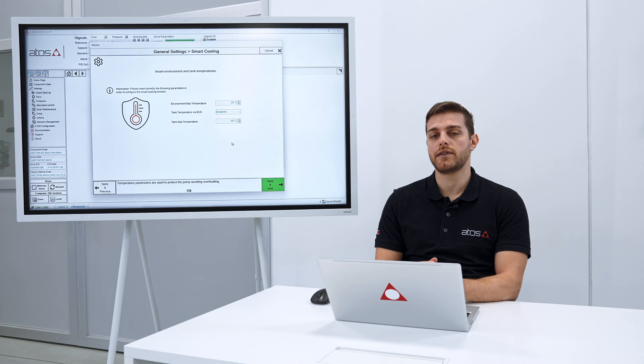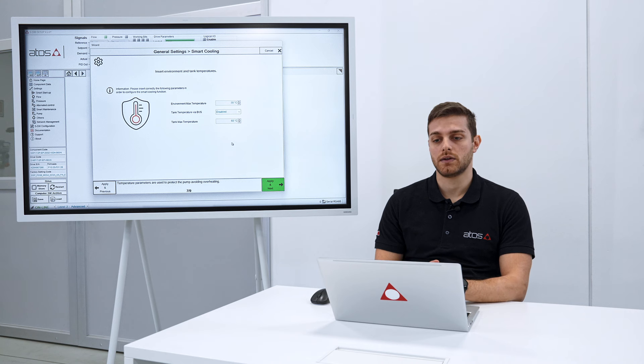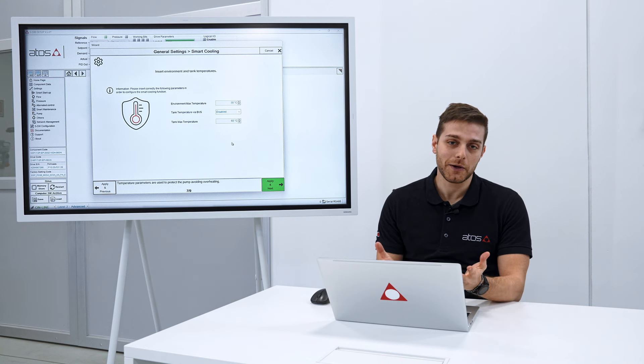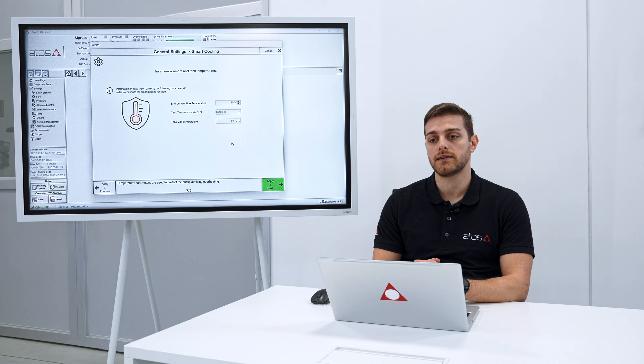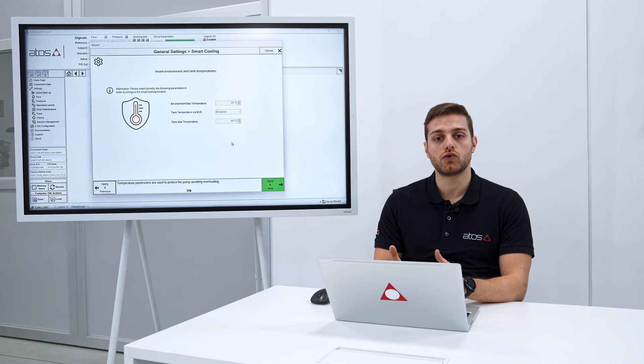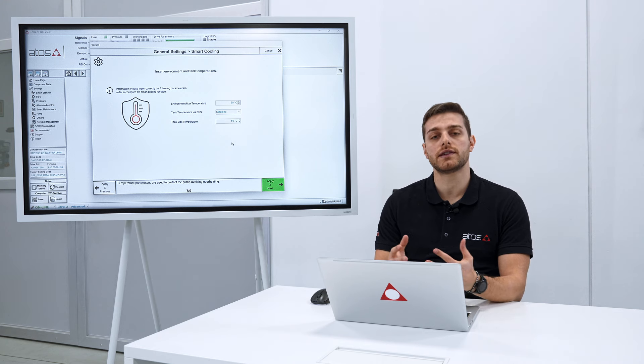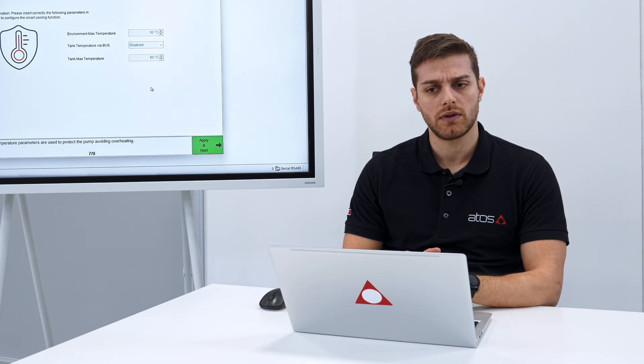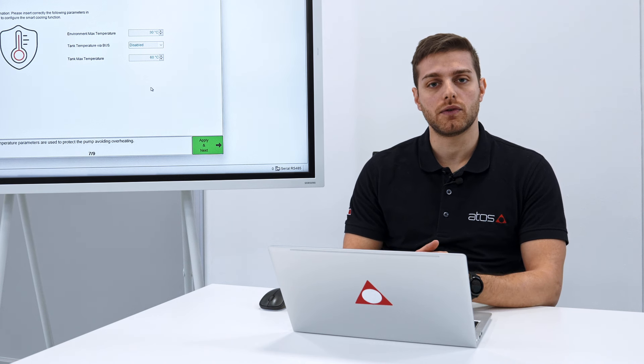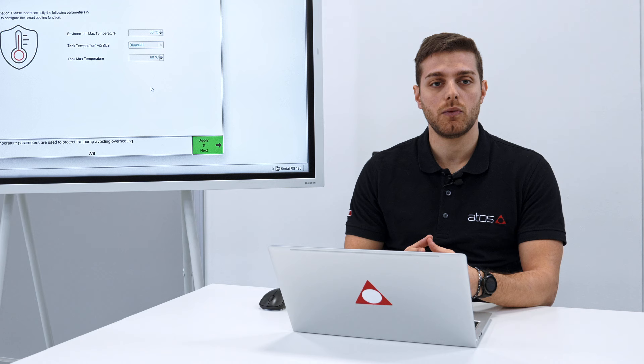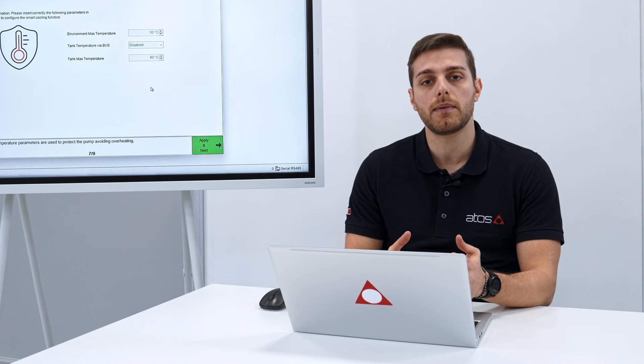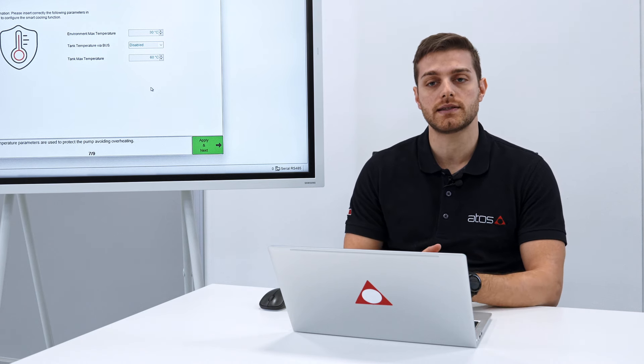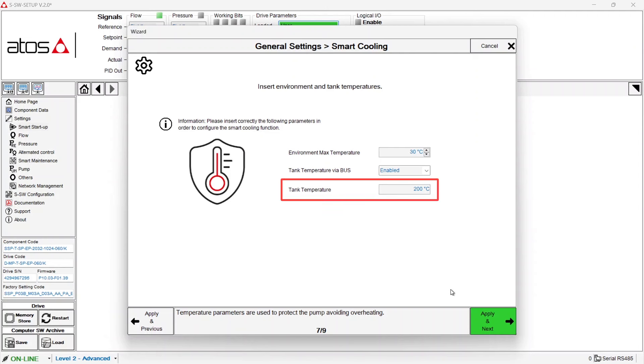Here instead we have the page dedicated to smart cooling. This functionality is a really cool one, it's protected by a patent and it allows to avoid the overheating of the servo pump. This is an option and is really useful for those machine cycles which are characterized by long static pressure control phases. To enable it you just need to insert the max environmental temperature and the max tank temperature. Once you have done it you can just go on.